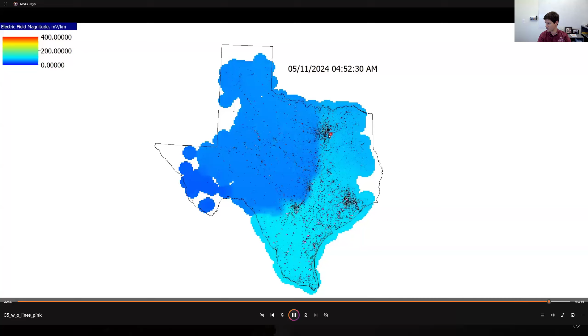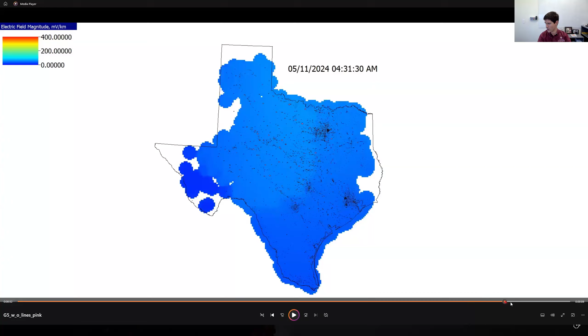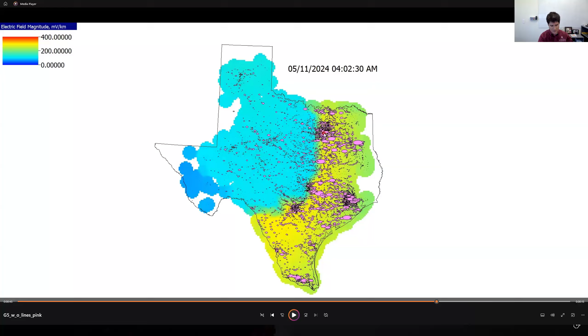Right around 3-4 o'clock in the morning, you can see how the GIC flows vary in the system. Even at the minute level, the GIC flows vary quite drastically, as does the E field. Keep in mind, this is Texas, so we're talking less than half a volt per kilometer, but in some of the more northerly states they were seeing several volts per kilometer calculated E field. This was calculated by NOAA, taking the B field measurements and running them through their B-to-E calculations. Let's go back to my slide.